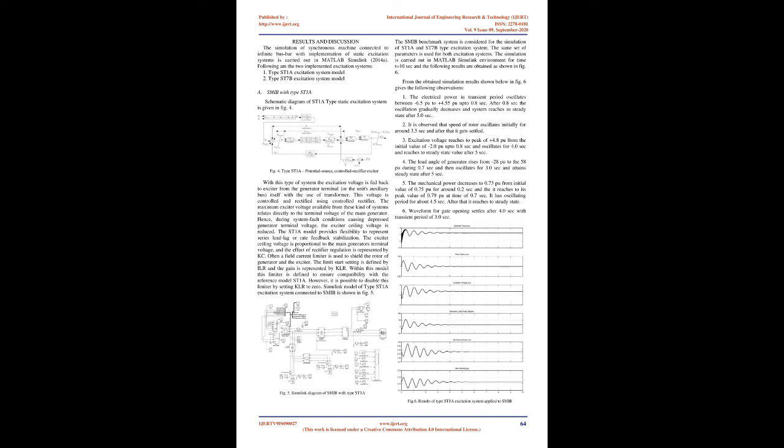A DC excitation system consists of the pilot exciter and main exciter. The output of the exciter is governed by an automatic voltage regulator, AVR. This regulates an alternator's terminal voltage at the output side. The current input of the transformer given to the AVR will reduce the current of an alternator during malfunction. When the circuit breaker at the field gets open, the field discharge resistor gets parallel with the field winding so that it will discharge potential energy in the highly inductive field winding. The main shaft drives the primary and the pilot exciters, or it is driven by a motor separately.